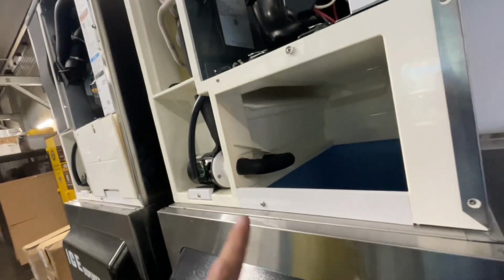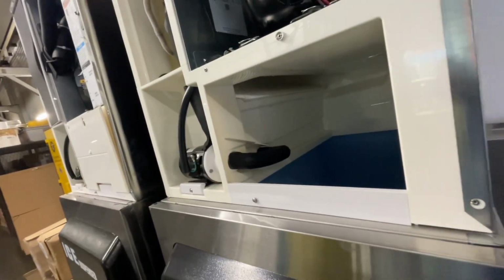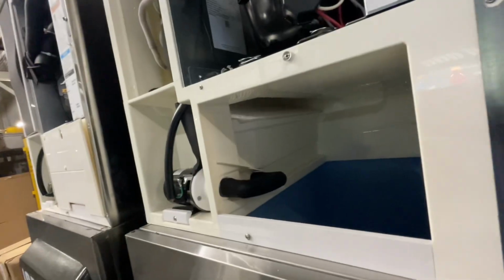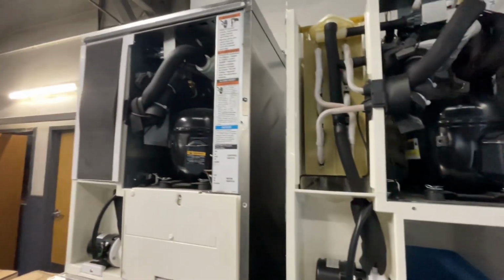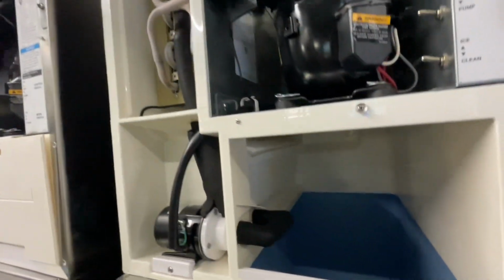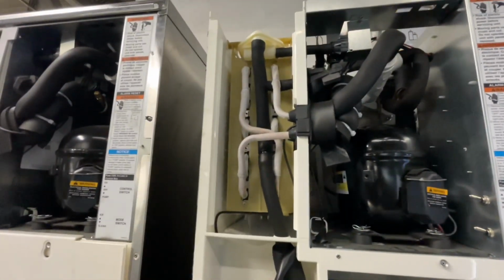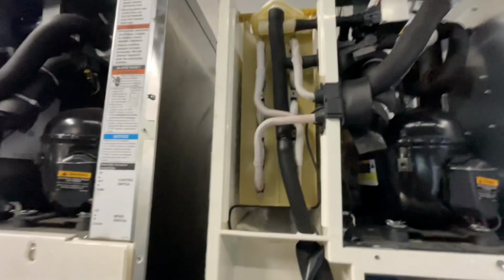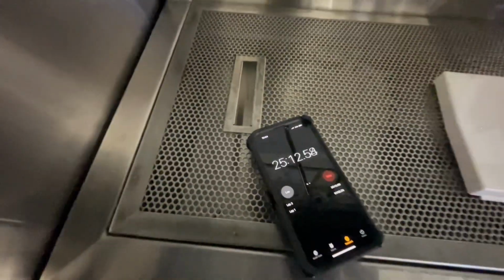So when the water flow down the length of the evaporator isn't high enough, usually you experience a freeze up. That's what I'm thinking happened, and it just took us too long to get here, or too long for them to call us in, and now all the ice is melted out of there. So we're 25 minutes into freeze on this machine.